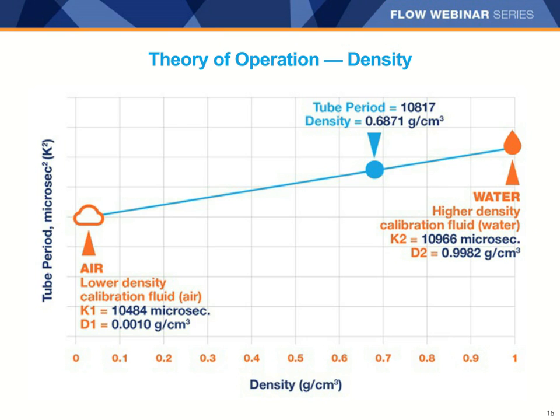Density calibration is performed at the factory on air and water. Meters are filled with air, resulting in a tube period of 10,484 microseconds in this example on the slide. Next, the meter is filled with water, which results in a tube period of 10,966 microseconds. These 2 values, which are called K1 and K2, are plotted against the density of the 2 fluids the meter is calibrated on, in this case, air and water. D1 is the density of air, and D2 is the density of water. The transmitter stores these values and automatically calculates the fluid density based on the measured tube period.